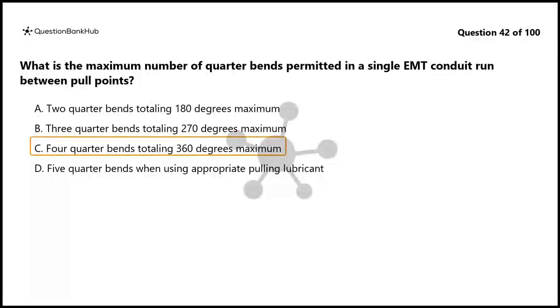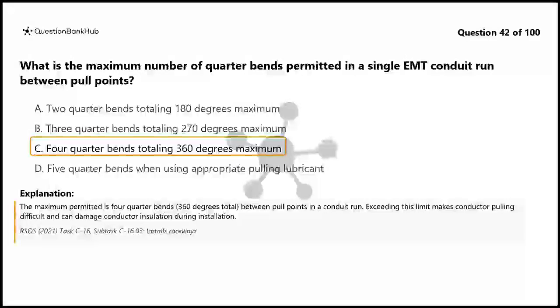The correct answer is C. 4 quarter bends totaling 360 degrees maximum. The maximum permitted is 4 quarter bends, 360 degrees total, between pull points in a conduit run. Exceeding this limit makes conductor pulling difficult and can damage conductor insulation during installation.